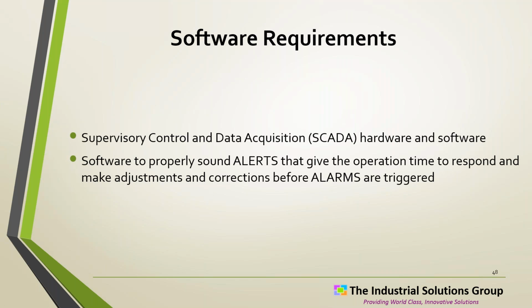On the software side, a lot of times this is already installed. So maybe there's an extra board, maybe it's another model that needs to be upgraded. But there are a lot of SCADA systems in operation, and they have some capability to do a better job of trying to turn data into knowledge. And we can certainly get alerts and alarms, and in fact people already do a lot of that. Primary alarms, secondary alarms, that's really what we're dealing with. A lot of those features are built in as part of core functions, but the programming just needs to be thought through.